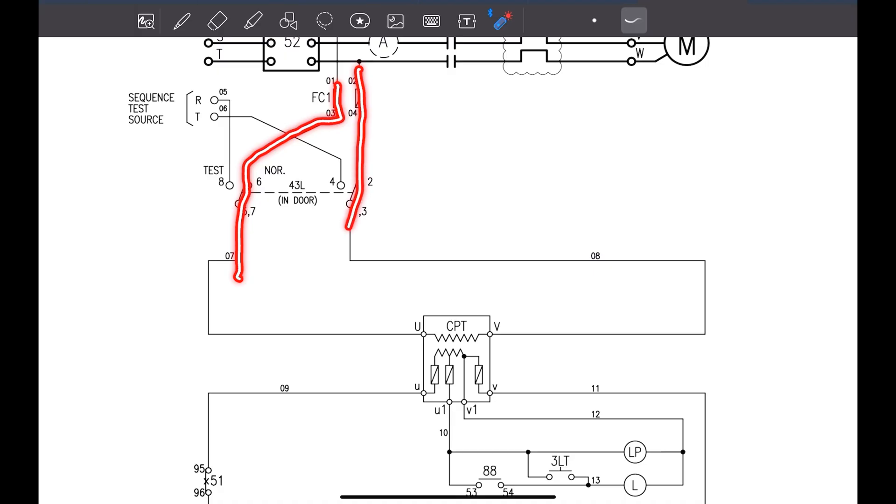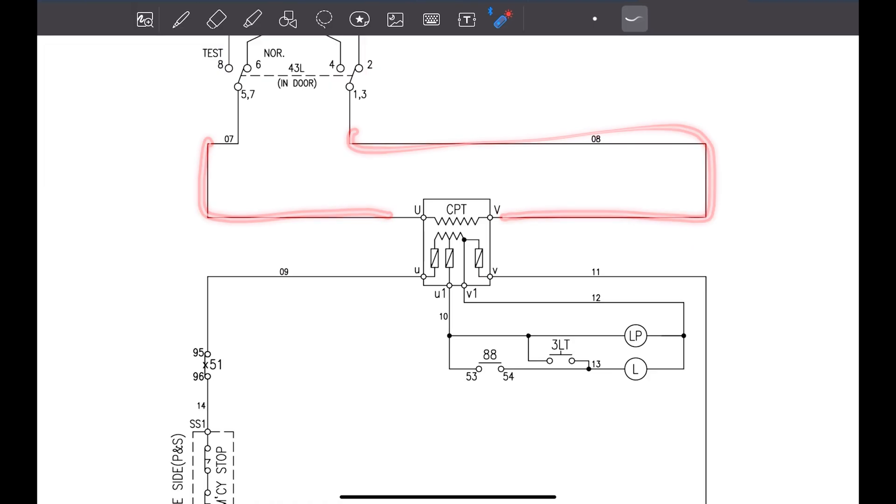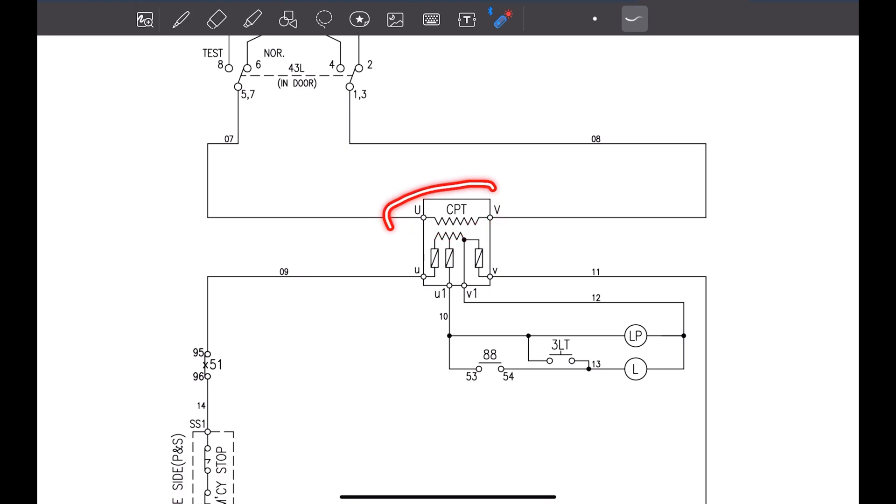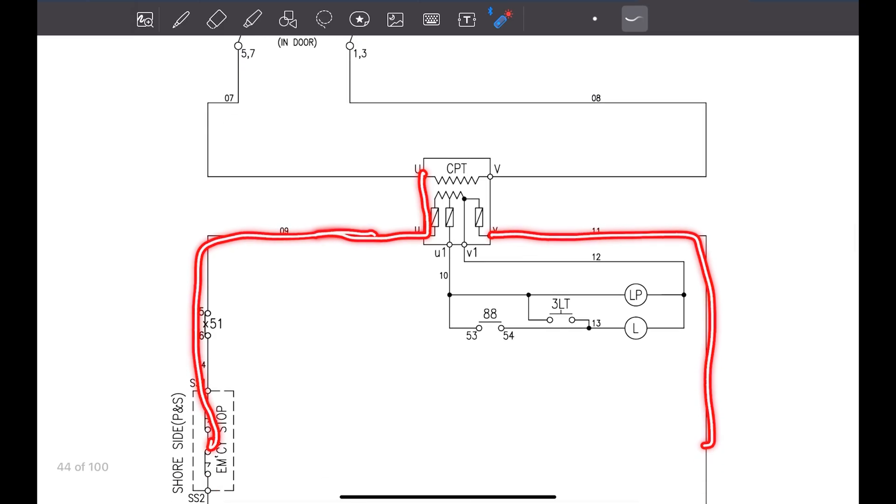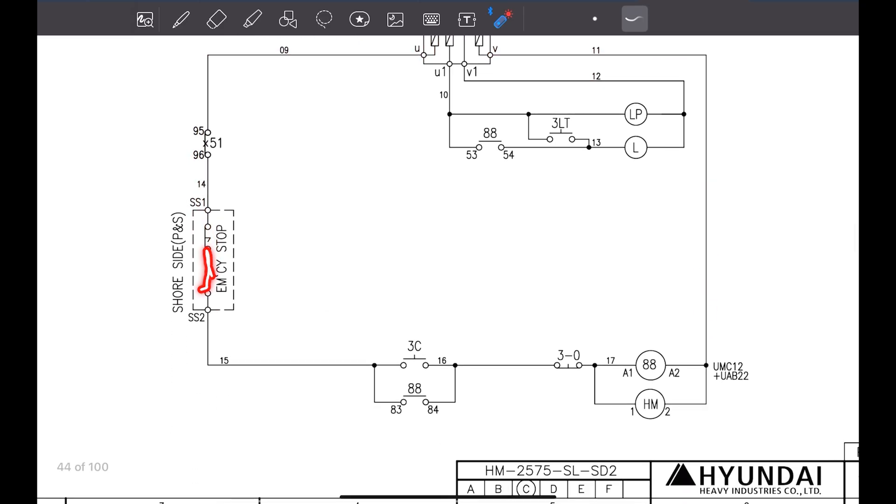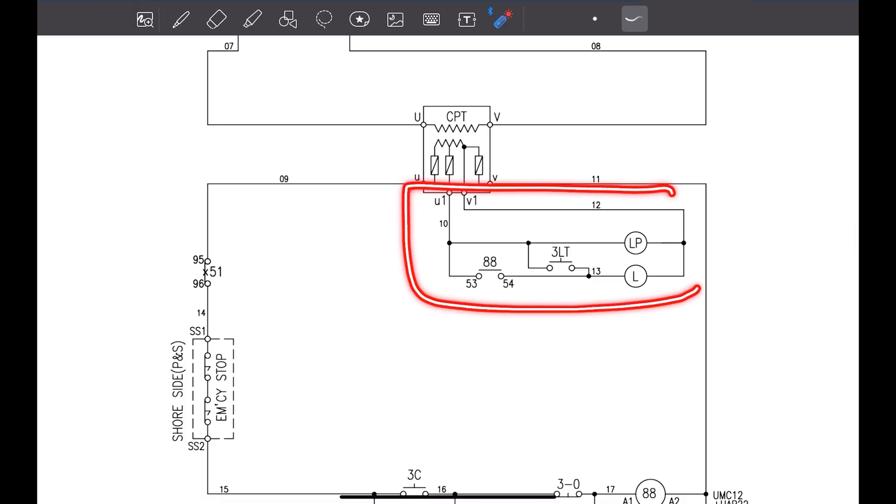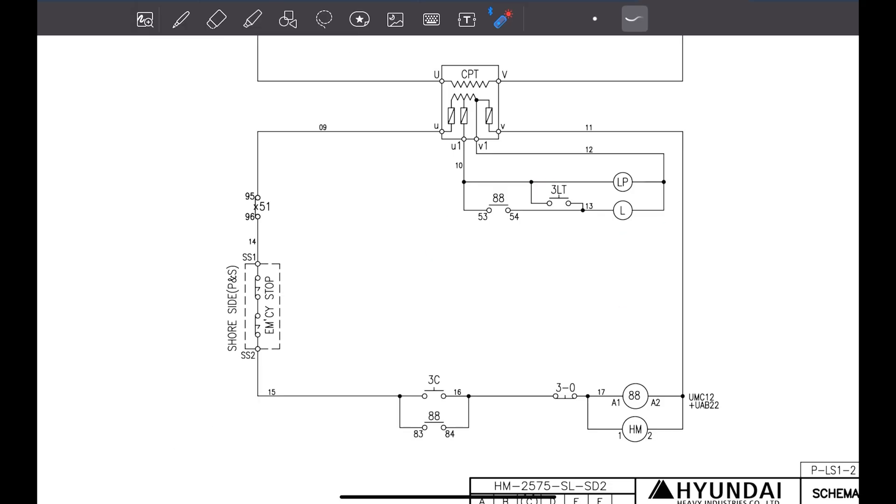Now we are going only in the normal operation mode. Power supply is coming from here. With these two lines the power is coming to the transformer. This is a 440 input. This is primary side of the transformer receiving 440 voltage. Now, this is stepping down the voltage in two parts. One is 220 that is going for the starting of the motor. This control part. And another it is stepping down to either 12 volt or 24 volt. This is for the lamp. This is the source lamp and this is the running lamp. This is having lower voltage.